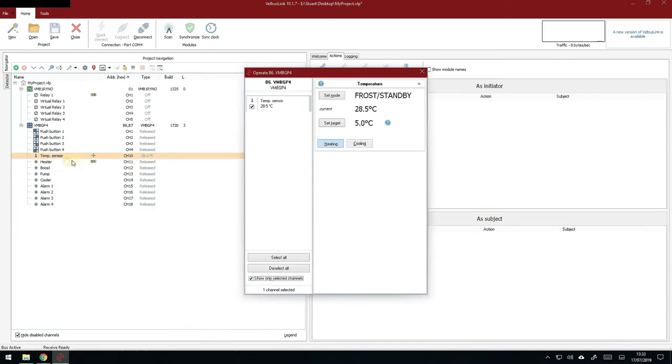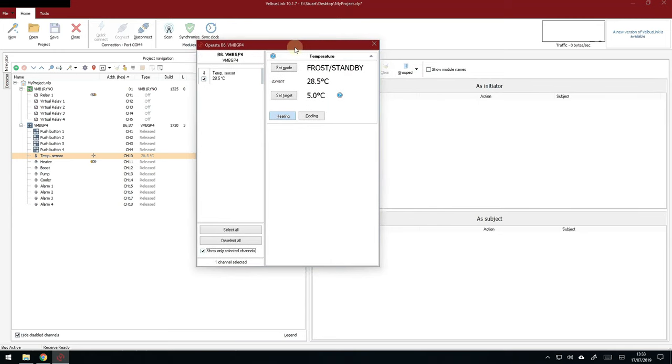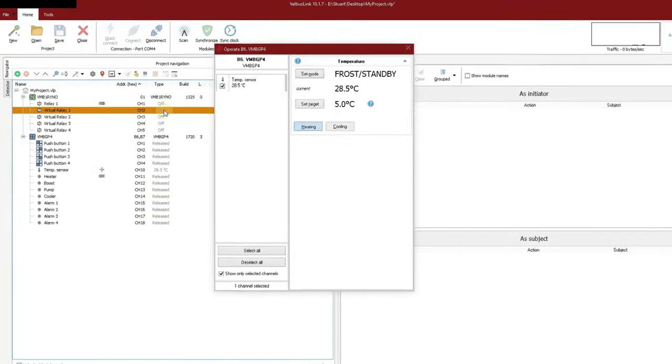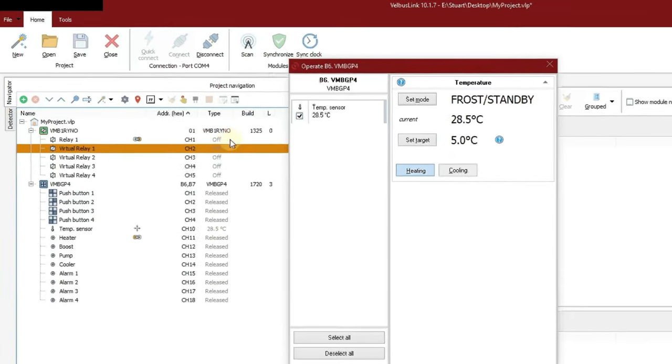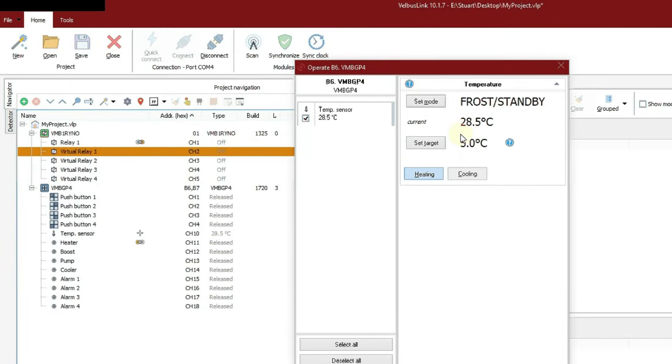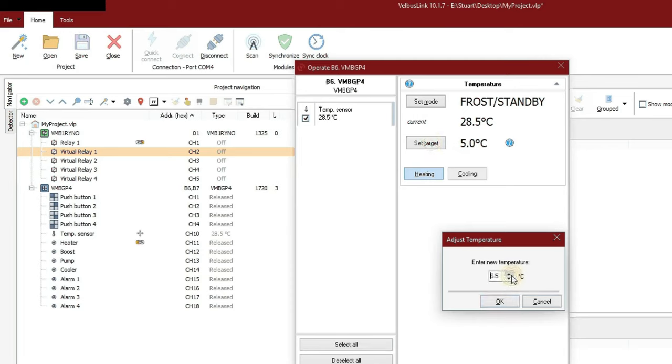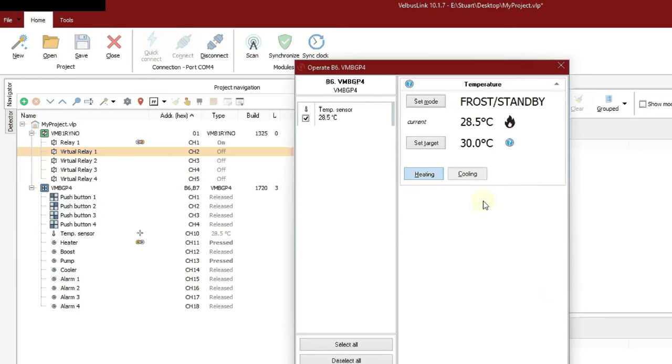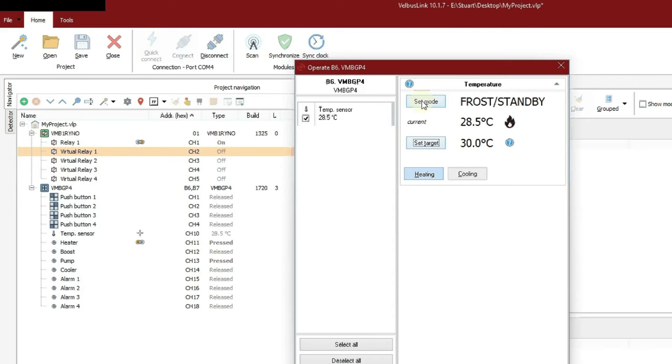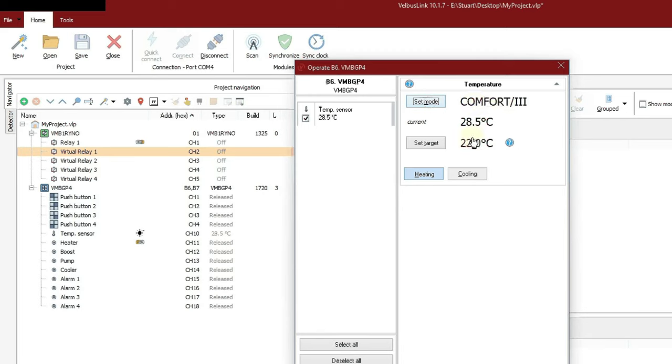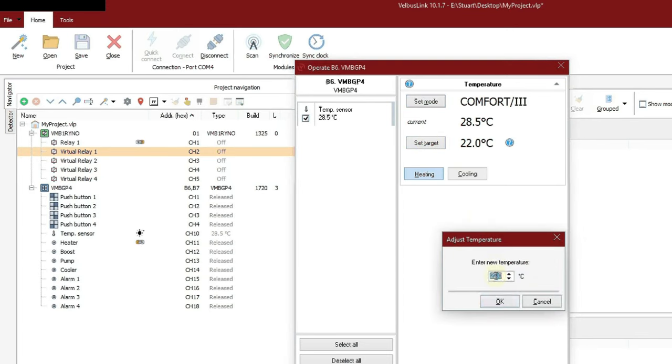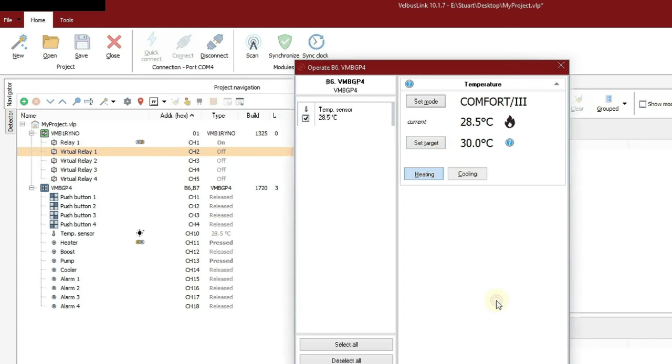Now if we right hand click and choose operate, we'll bring this little window up. And we can now scroll through all the heating modes. I'm going to highlight underneath that relay so that you can see when it's coming on and off. Now 28.5 degrees in England in July is pretty good going. So we're going to need to do some manual overrides here. So if I set the target temperature to 30 degrees, it's probably quicker to type it in. See straight away it comes up as demanding for heat. The heater's pressed and the pump's pressed. And if you look right at the top relay one is on. As soon as I change mode it'll go off. And the target temperature is changing to 15. Day 20. Comfort 22. These are all programmable and adjustable. So let's just adjust that back to 30 just to show it's working again. There you go. Heat demand. Relay on. Change the mode and it goes off again.